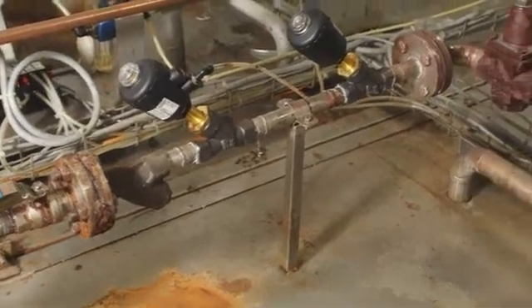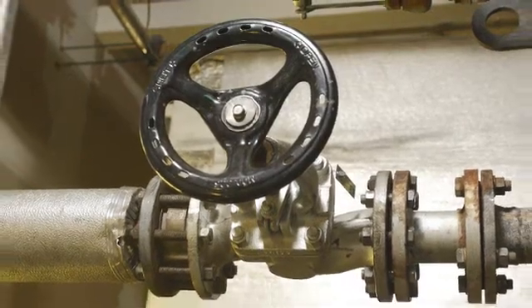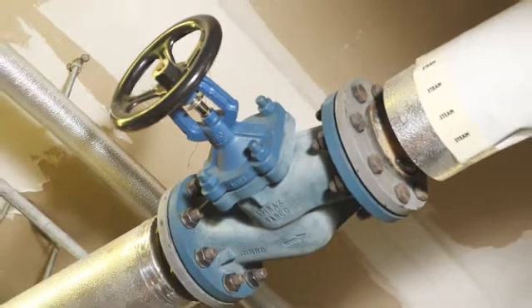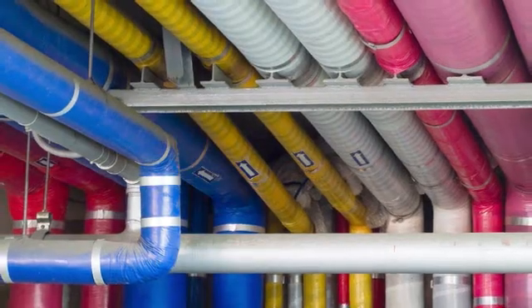Steam or hot water pipework and fittings should be insulated to prevent energy from being wasted. The main isolating valves on and around the steam boiler are large and invariably not insulated. A valve can waste the same amount of energy as 1 metre of pipe. After repairs or modifications have been undertaken to steam or hot water pipes, it is important to replace the thermal insulation.